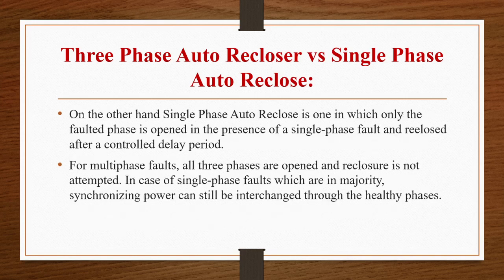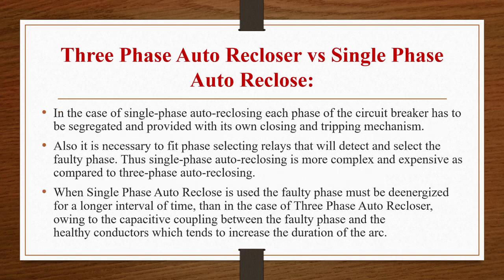On the other hand, single phase auto reclose is one in which only the faulted phase is opened in the presence of a single phase fault and reclosed after a controlled delay period. For multi-phase faults, all three phases are opened and reclose is not attempted. In case of single phase faults, which are in the majority, synchronizing power can still be interchanged through the healthy phases.